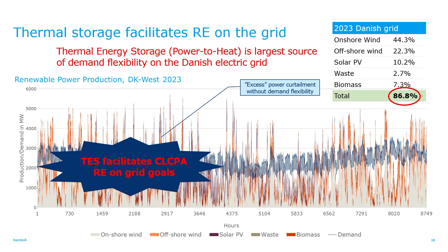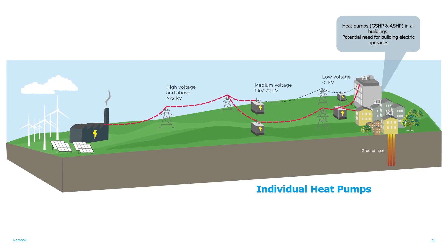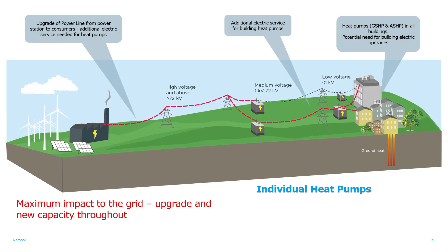If we go to an individual heat pumps solution, we will need heat pumps in the buildings and the electrical capacity to accommodate that, which will mean upgrades throughout the system. This represents the maximum impact to the grid, especially if you used air source heat pumps. With a 5G system, we will still have heat pumps in the building, potentially requiring electrical upgrades, but potentially not as much as the individual building case because of more efficient heat pumps on a 5G system and the thermal inertia.